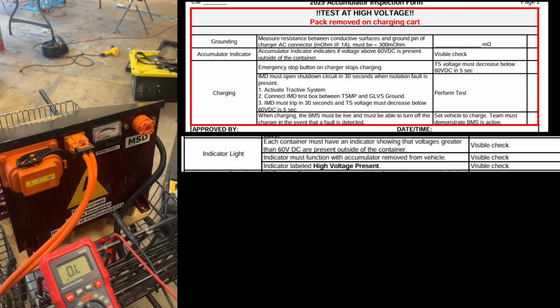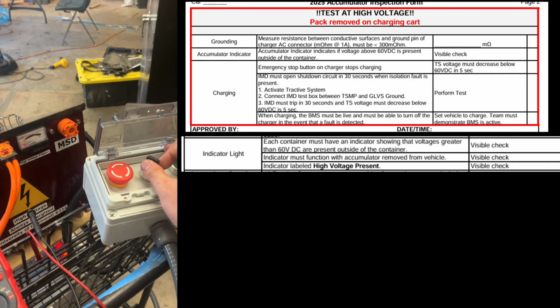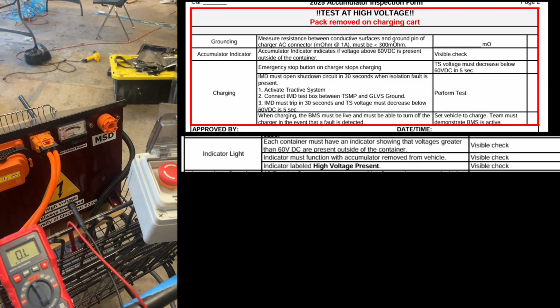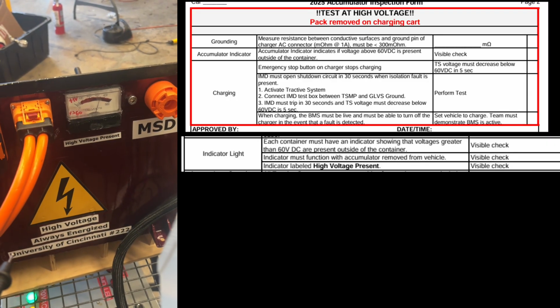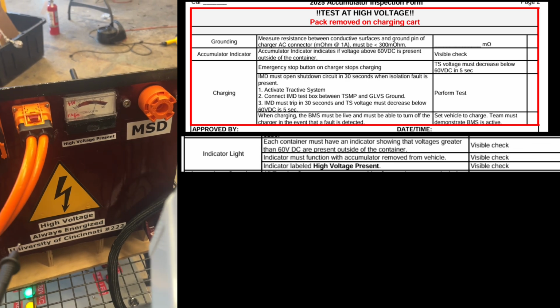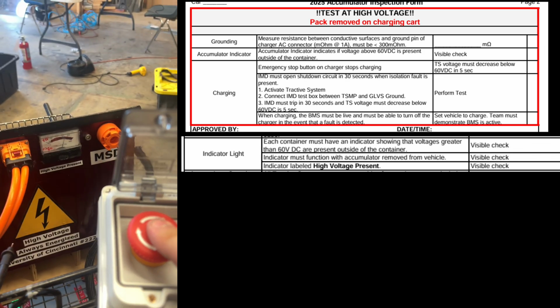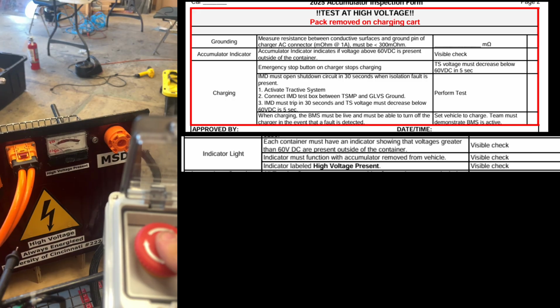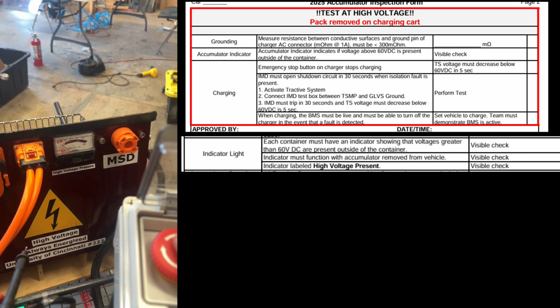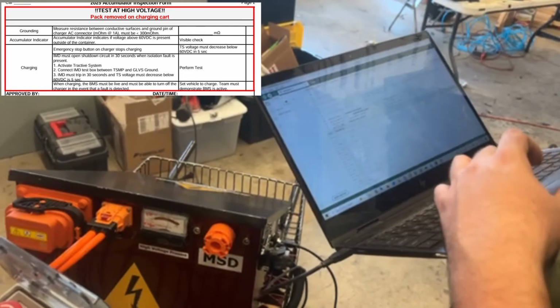Here we have our charger on the charging cart. Right after startup, we will turn the charger on, clear faults, and it turns on. You can see that our voltage indicator is working, indicating above 60 volts. When we hit the E-stop, like so, it discharges to less than 60 volts in much less than 5 seconds. We're currently charging.